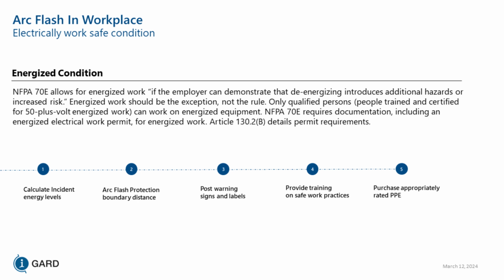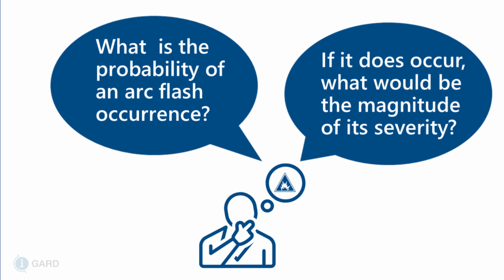We have 50 volts for energized work. If you have more than 50 volts, 70E requires documentation including energized work permits for energized work, and Article 130.2(B) details permit requirements. So the onus is on the employer here to ensure that they authorize the employee to perform work energized. The onus is changed from the employee. You have to protect the employee, but the employer, who assumes the responsibility if that person gets hurt, has to authorize the work. But everything else needs to be done as well, so no one else gets hurt. And gets hurt, period. That's what we want to do.